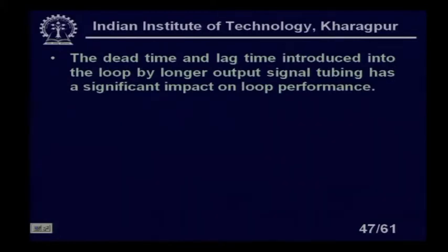The dead time and lag time introduced into the loop by longer output signal tubing has a significant impact on the loop performance, because whenever we are using tubing in pneumatic systems, it is not very predominant in the case of electrical systems, but in pneumatic systems we are using more tubing. Obviously, it will increase the lag in the system as well as the dead time in the system.